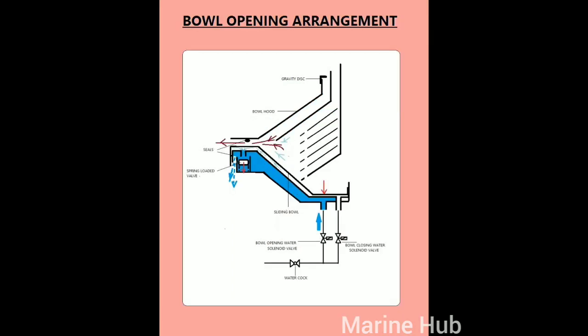Bowl opening operation: Once the predetermined time is reached, the bowl opening solenoid valve will open for a certain time period programmed by the operator. The water will enter into the opening water chamber.